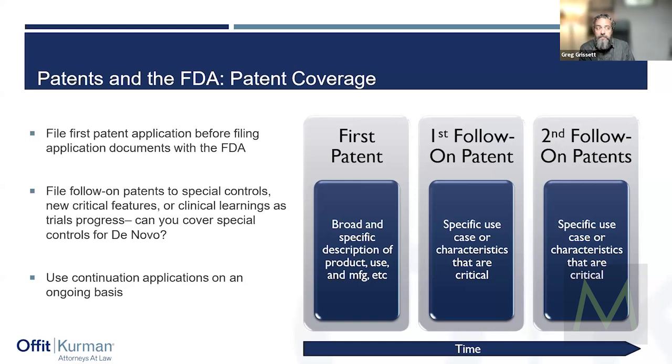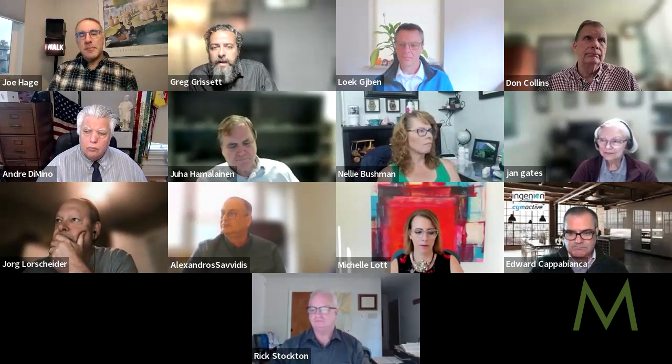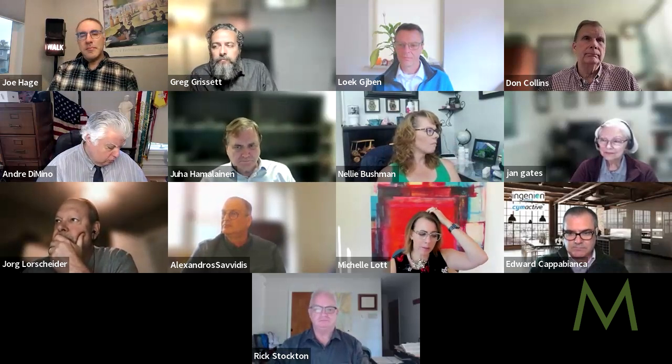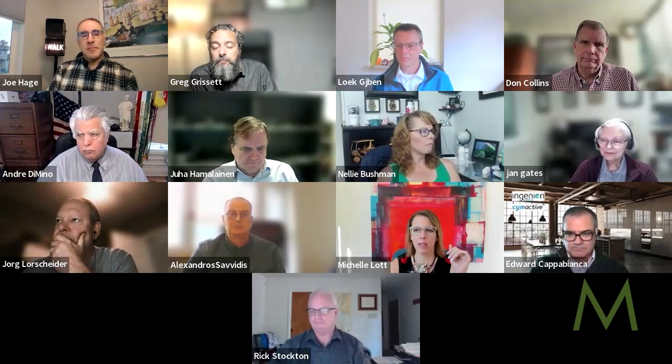I've had a couple of clients weigh de novo versus PMA, and they've gone with the de novo route. I'm not sure what the timing is. I don't know if they're taking a longer time now to do the de novo than they had a few years ago, or how that relates to the PMAs, at least right now. I think the average, the last time I looked, was 400 days for a de novo and 800 for a PMA.